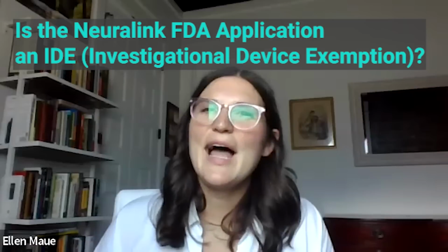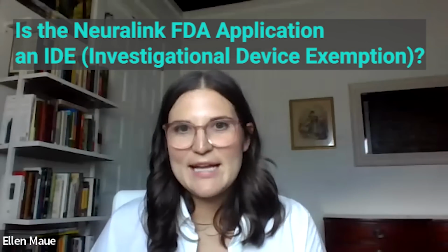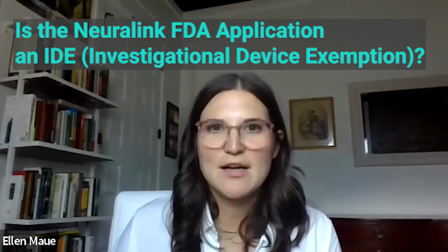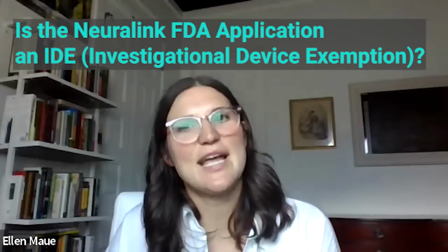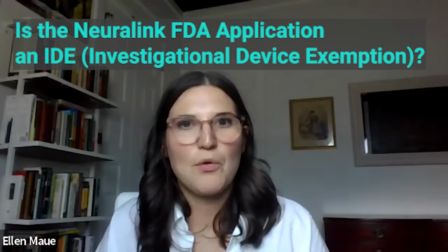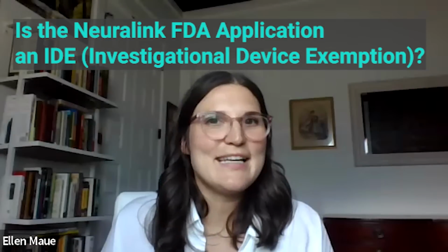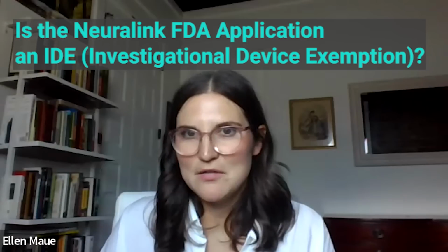When Elon says that Neuralink has submitted their FDA application, do you think that's the IDE? I do think it's the IDE. However, the FDA's timeline to return comments on an IDE is 30 days, unless they have questions or concerns or issues with the IDE. So if an IDE has been submitted, it's likely in ongoing negotiations. The way an IDE works, you submit it and the FDA has 30 days to respond to you. They can either respond with an affirmative, not respond within 30 days, which is considered an affirmative, or they respond with questions, concerns, requests.